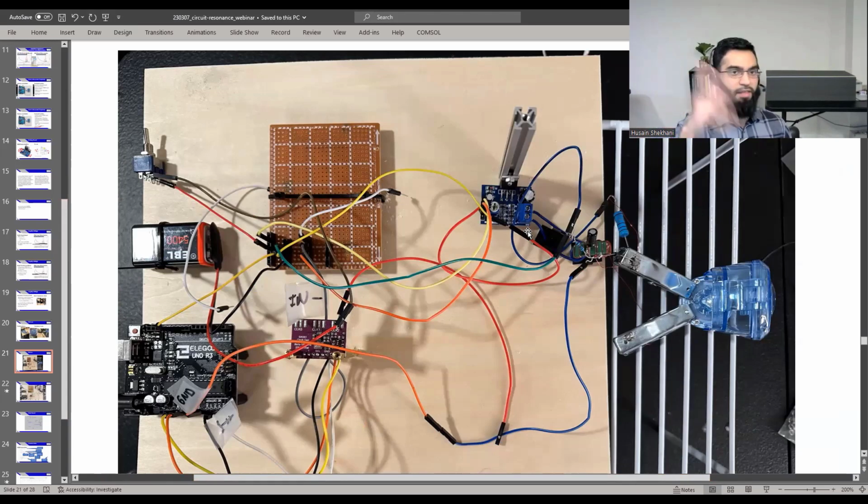There are mathematical equations, and based on experience and testing, you can know how much voltage and current from the primary side and what the phase is going to be on the secondary side on the transducer. Some of that can be calculated, but for practical purposes, you can just do the measurement. There's going to be a higher level of abstraction too when you take those measurements, put them in the microcontroller, and do some control around it. So that's the case there.